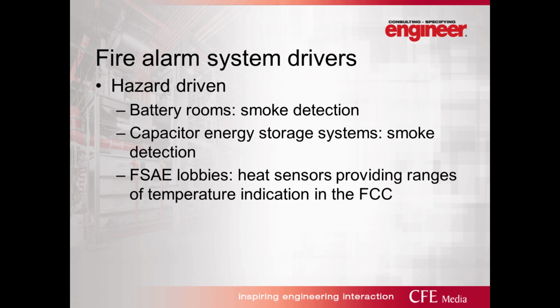And then we also have specific requirements for what's known as fire service access elevator lobbies. Those are required in buildings that have floors that are over 120 feet above the lowest level of fire department vehicle access. They're hardened shafts. There's a whole slew of requirements in the building code on these. But an additional requirement is that heat sensors be provided in the lobby that identify the temperature ranges and report back to the control panel in the fire command center.